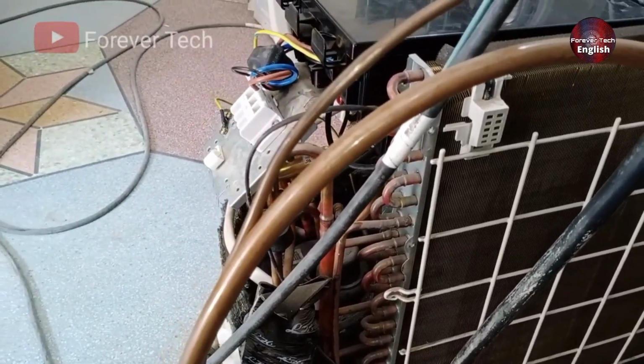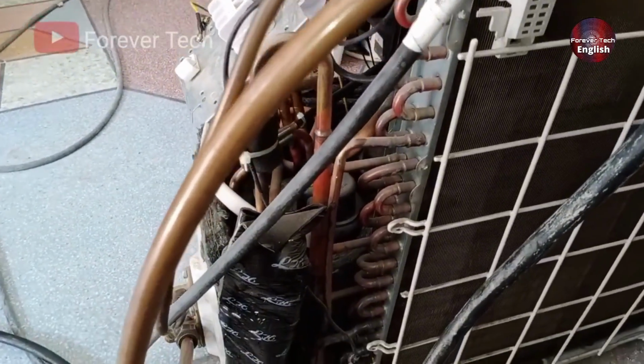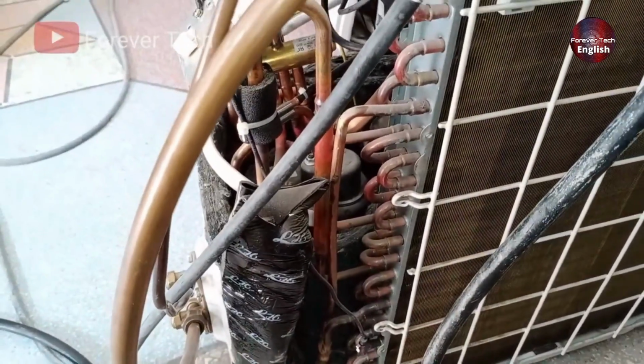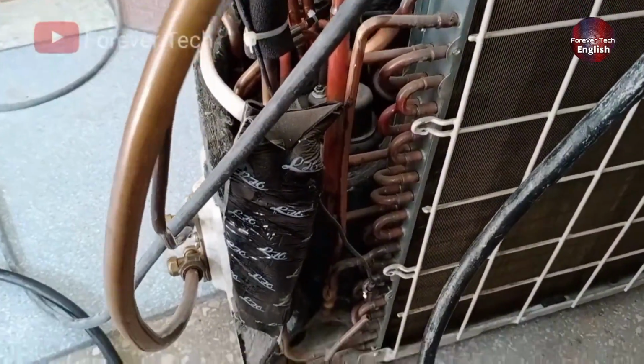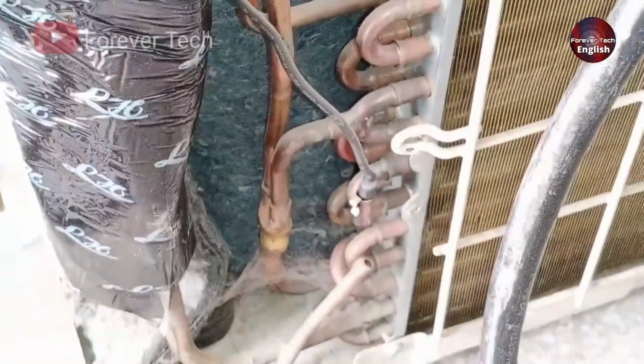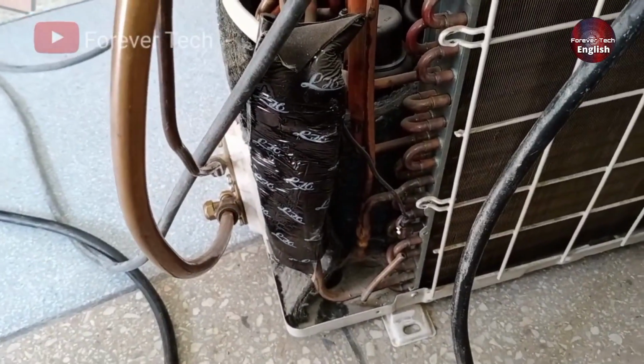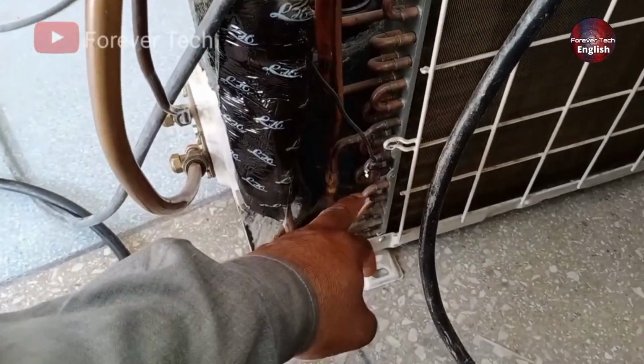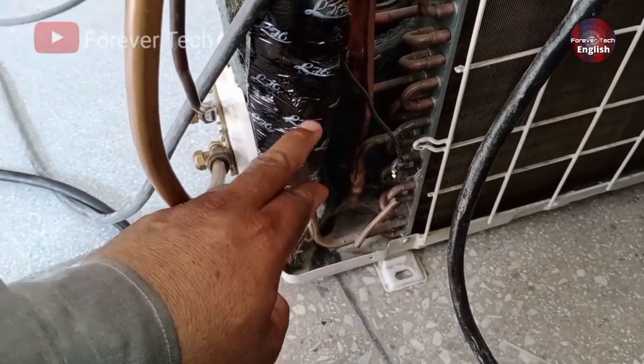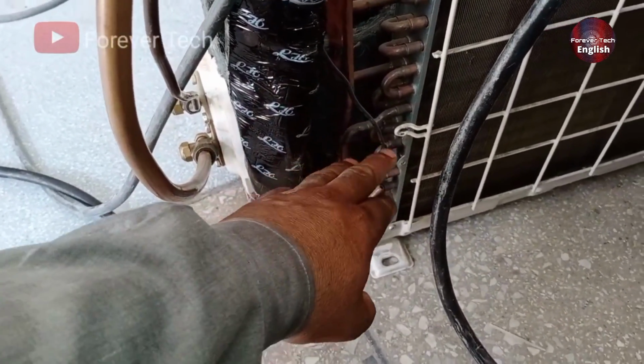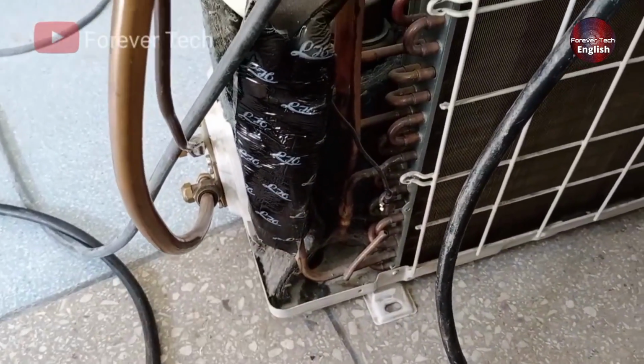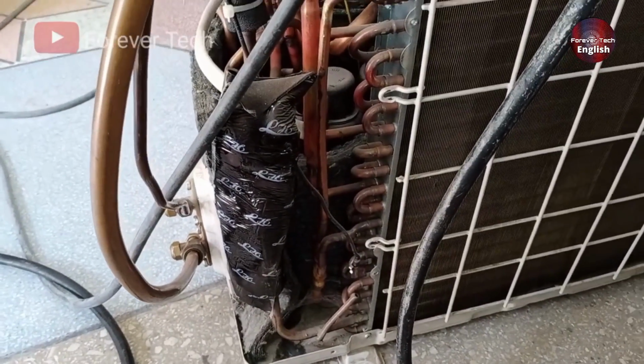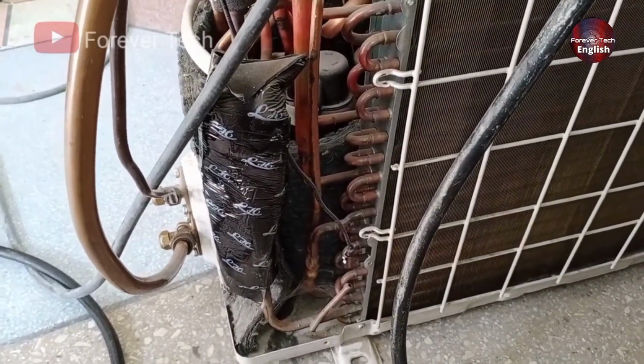I've opened the cover to show the position of the condenser pipe sensor. Now, we can see the entire condenser, including its pipes. As you can see, the sensor is attached to the liquid line. It's installed before the expansion, i.e., before the liquid converts to a gas. This setup allows us to measure the temperature of the gas in its liquid form as it enters. This way, we can ensure proper cooling and evaluate whether we're getting adequate cooling performance.